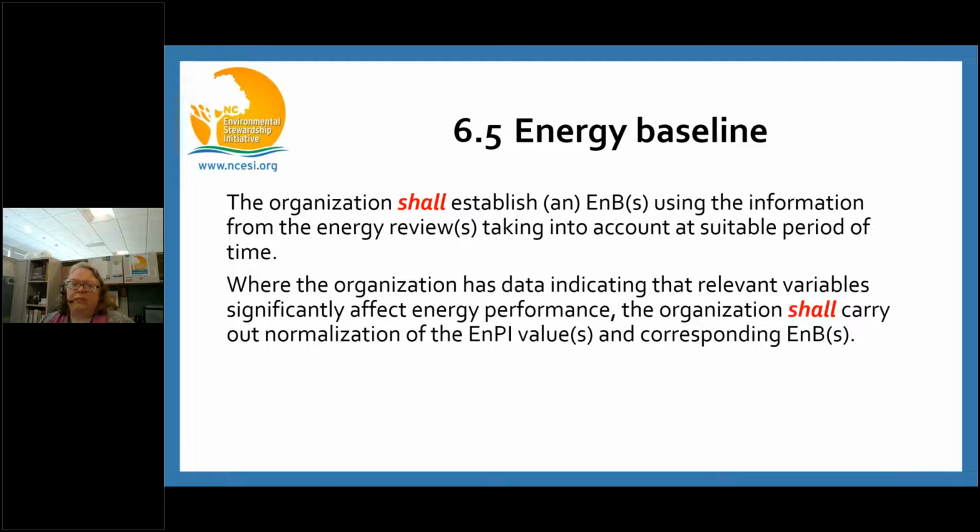So for example, if production rates significantly impact the amount of energy used, then you have to calculate the usage compared to the variable. So that would be like production or weather or employee work hours. It's how much energy is used per widget, or how much energy is used on a high heating day or a high cooling day, right? Or how much energy is used per employee work hour. How are you going to make that data make sense over time is basically what you're looking for. This comparison can help show progress even when actual usage is increasing.